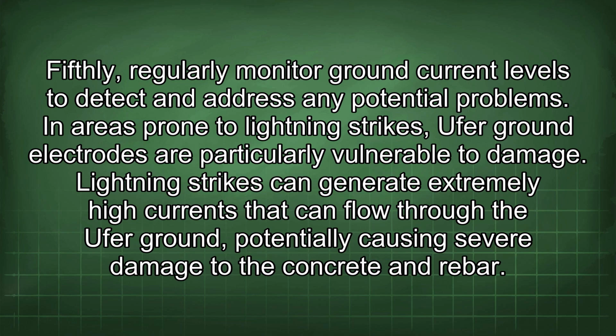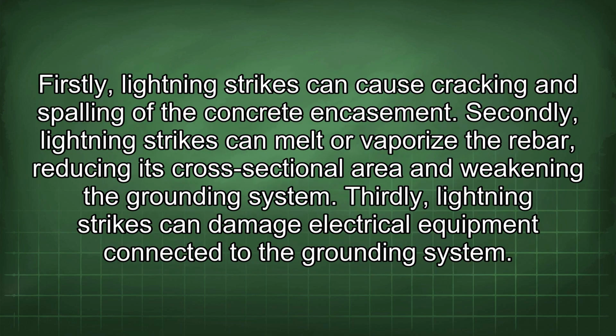In areas prone to lightning strikes, Ufer ground electrodes are particularly vulnerable to damage. Lightning strikes can generate extremely high currents that can flow through the Ufer ground, potentially causing severe damage to the concrete and rebar. Firstly, lightning strikes can cause cracking and spalling of the concrete encasement. Secondly, lightning strikes can melt or vaporize the rebar, reducing its cross-sectional area and weakening the grounding system. Thirdly, lightning strikes can damage electrical equipment connected to the grounding system.